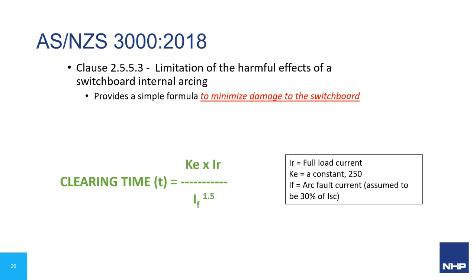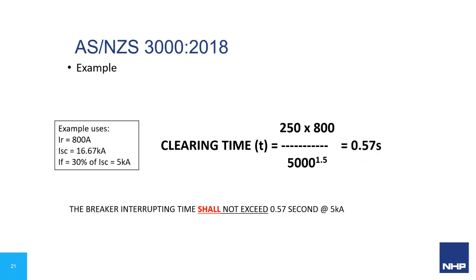So let's have a look at the actual example out of AS3000. 800 amp board, short circuit current of 16.67 kA. So 30% of that is 5 kA, which gives us a nice round number. And the clearing time it gives you is 0.57 seconds. So the breaker interrupting time shall not exceed 0.57 seconds at 5 kA. That's it. It's basically saying, do this and you're on the right track to minimize the damage. That's all it really goes into. There is a bit more to look at there, which we'll come back to for that specific figure that we've come up with there.